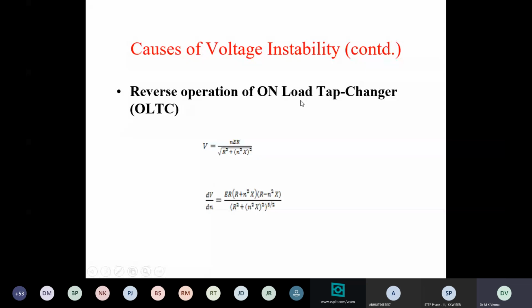So it means the tap changer is able to control the voltage, but it is not able to control voltage stability. It is deteriorating voltage stability. So this is not helpful in voltage stability control. So for voltage stability, at high demand, what you should do is block the tap changer.